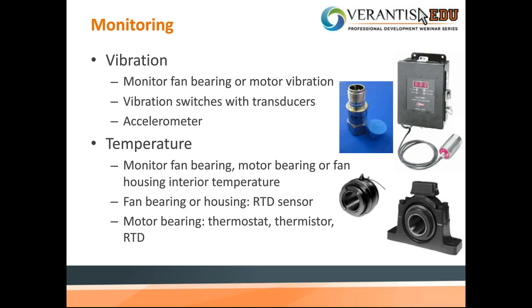So there's a couple different types of monitoring available. The two main ones are vibration and temperature. Vibration can be monitored on the fan bearing or motor, typically done with vibration switches with transducers or an accelerometer. Temperature monitoring can be done on fan bearings, on motor bearings, or actually on the interior of the housing. Fan bearings or housings are typically an RTD style sensor, whereas the motor bearings use either a thermostat, a thermistor, or an RTD sensor.